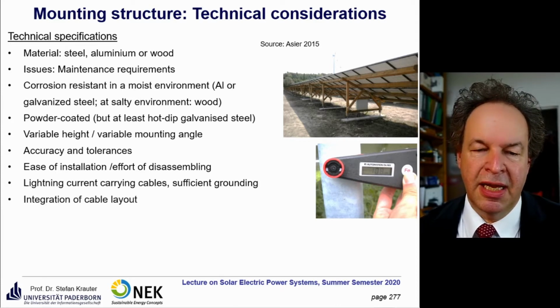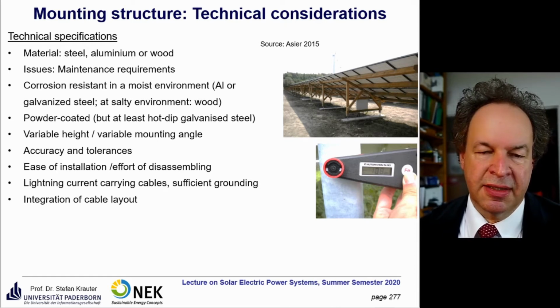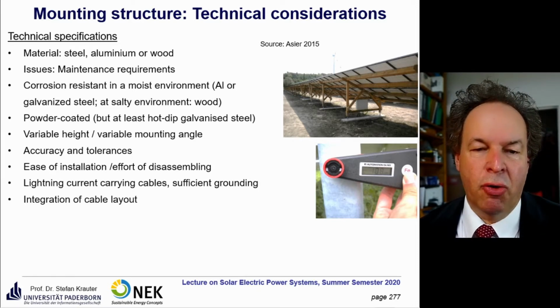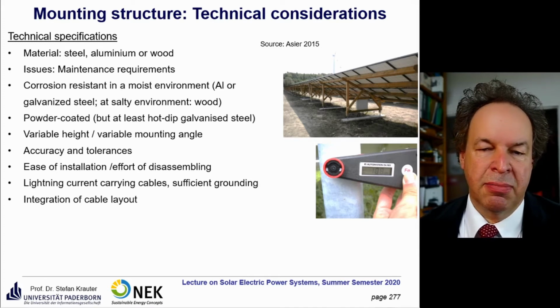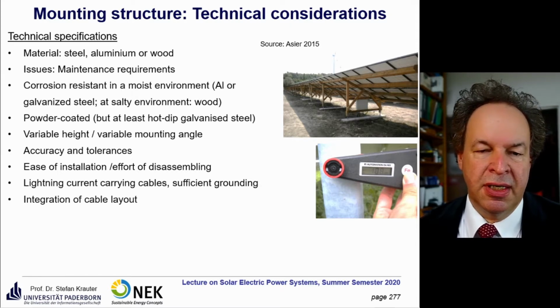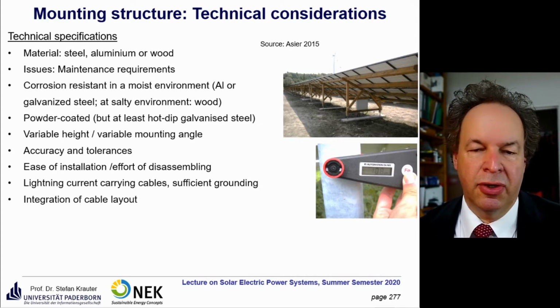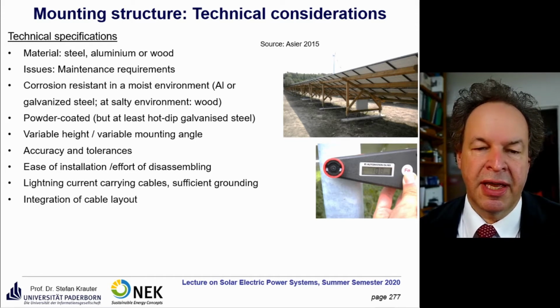Integration of the cable layout: you want to make sure cables are protected against UV radiation, wind, and attack by mice or other animals. In some countries it's even required by law to put cables in a housing. For example, in the United States, you always have to put cables in a metallic tube because many houses are made of wood and there's a fire danger, so all current carrying cables have to be encapsulated in a metallic tube.